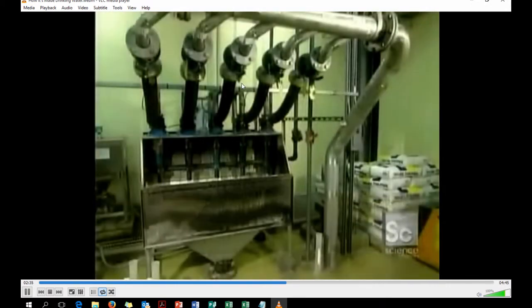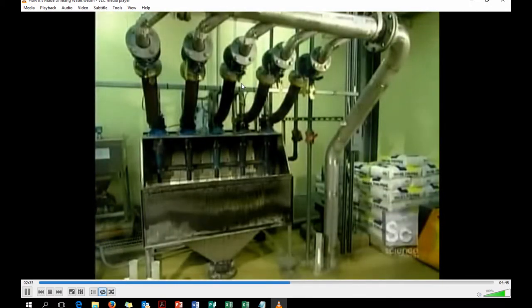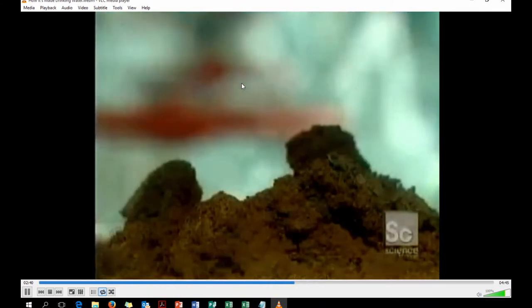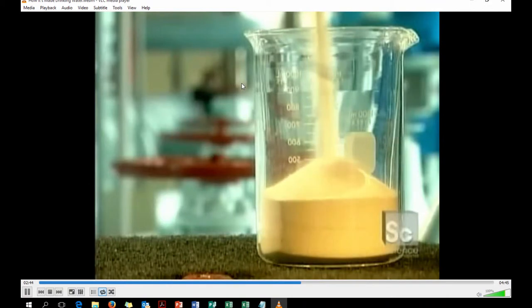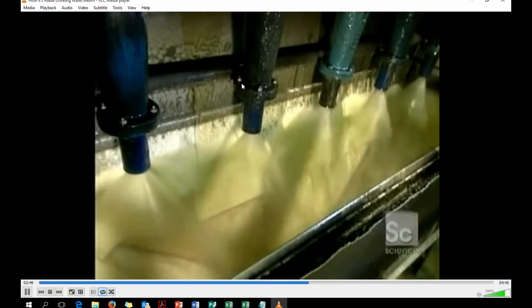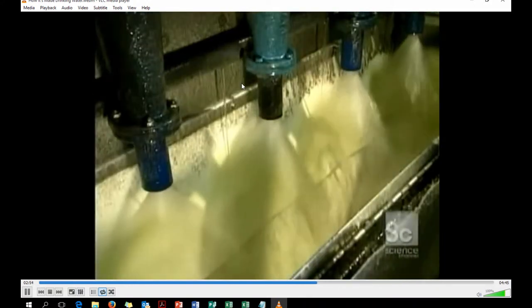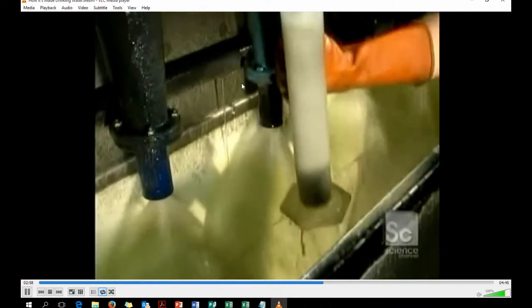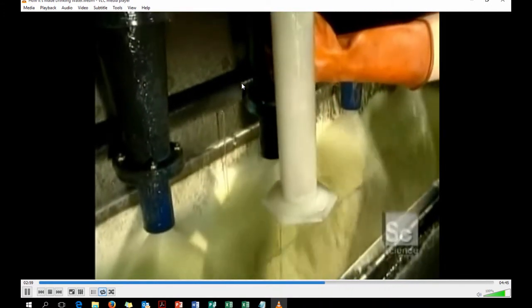Five pipes inject the water with superfine particles of sand called micro sand. The polymer coats the sand, making it sticky. The grains of sand then stick to the floc in the raw water, weighing them down even more. The water then flows into a settling tank, where the floc, because they are heavier, settle to the bottom.